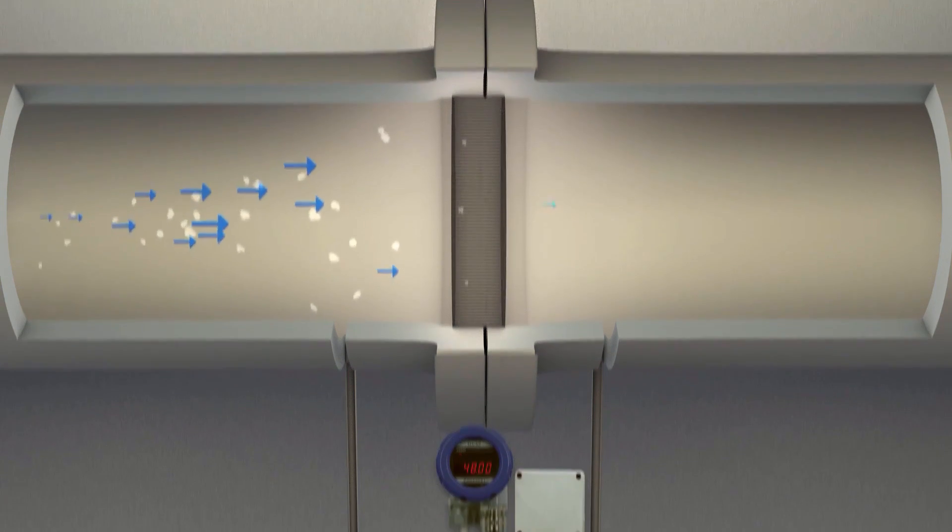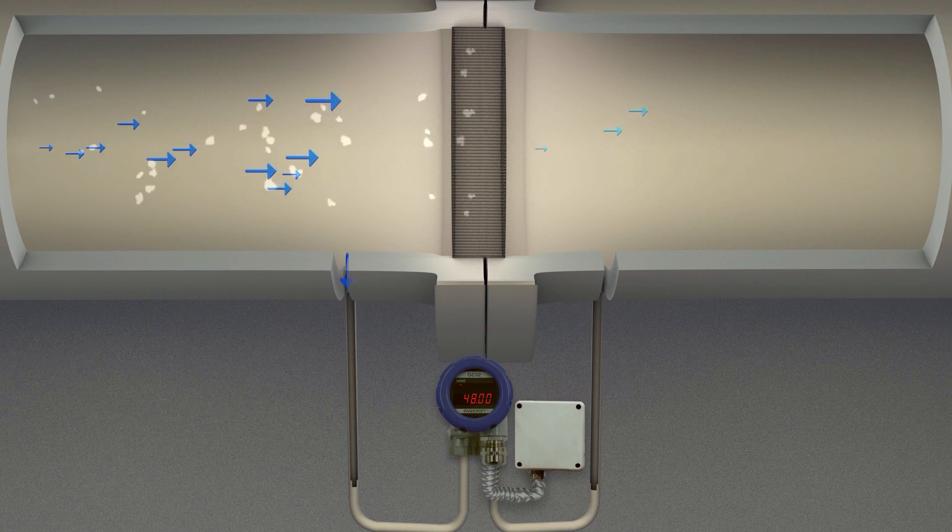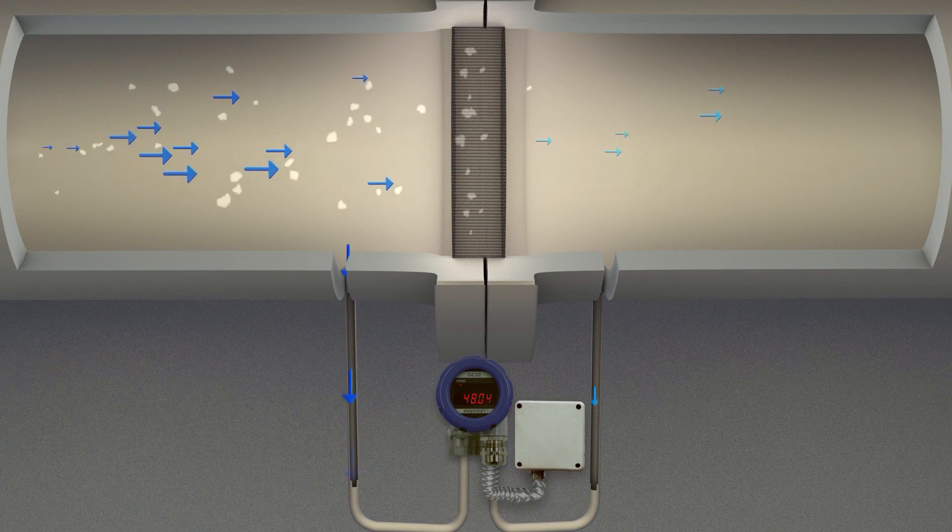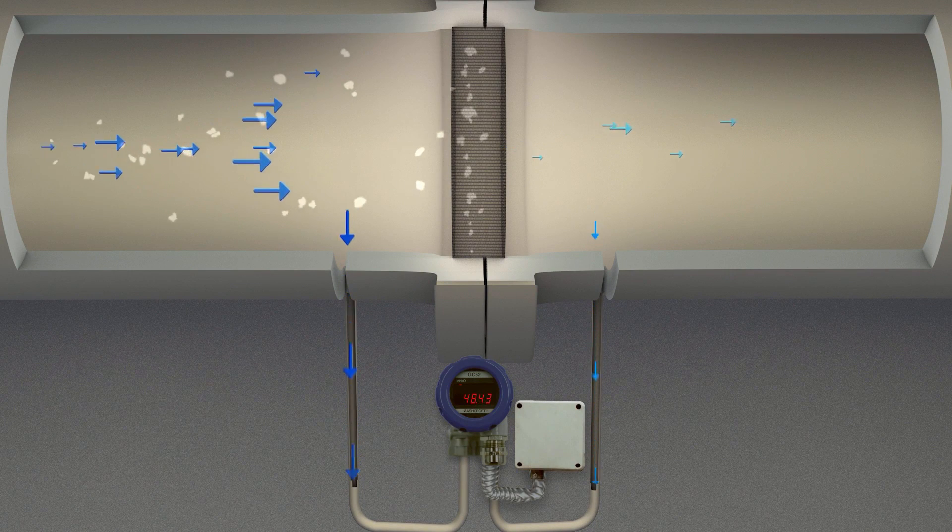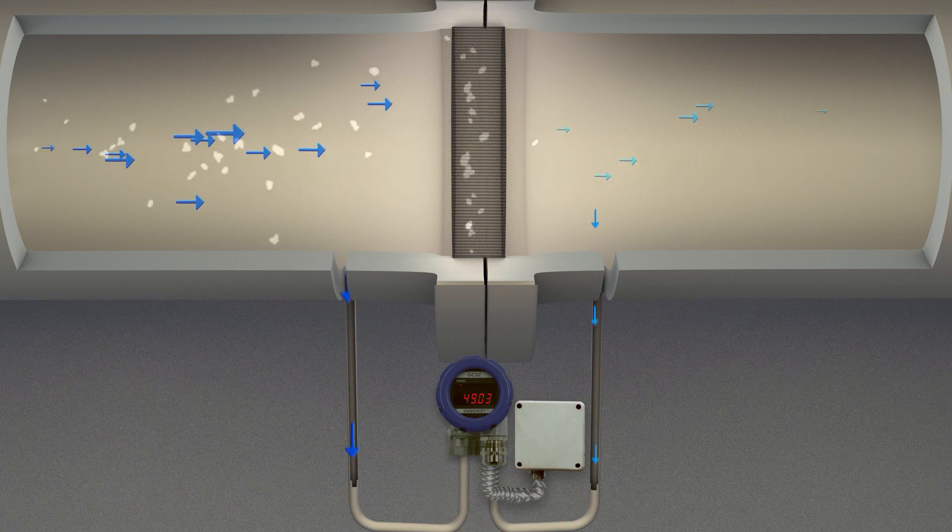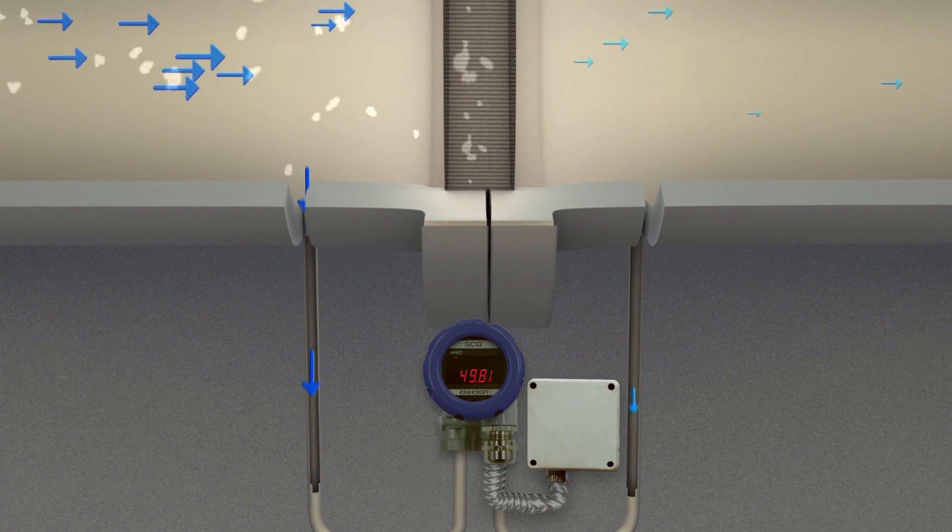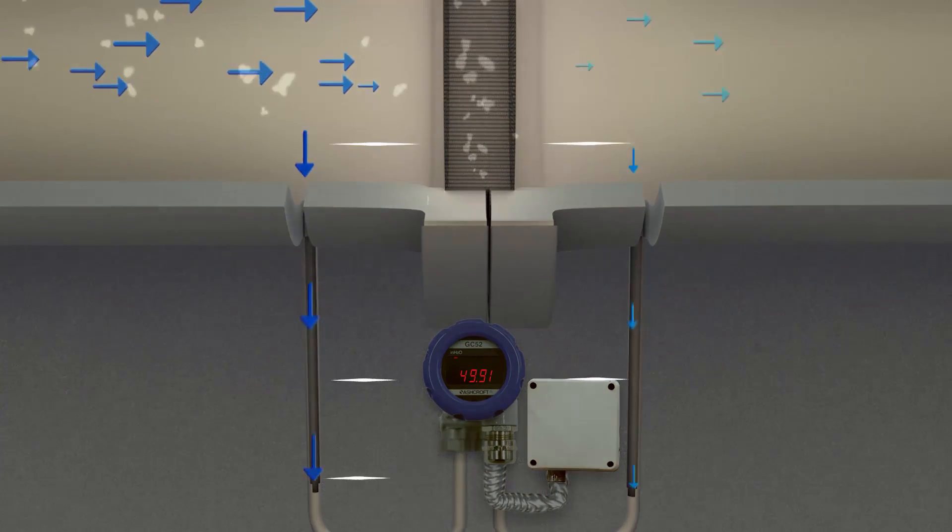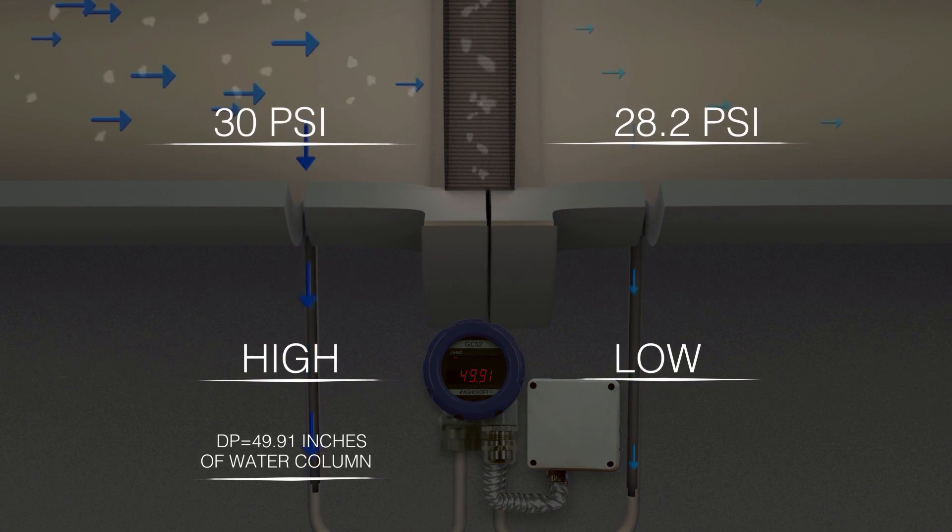Placing taps both before and after the filter, a differential pressure measuring instrument can be connected to detect the high side and low side pressures. The instrument will report the difference between the two sides. The saturation point will be indicated when the delta P value reaches a predetermined threshold.